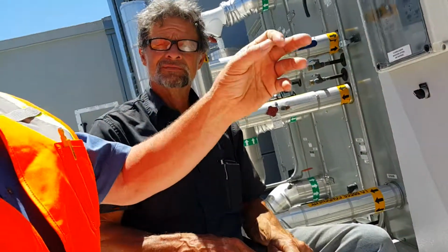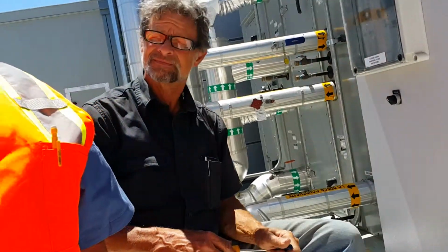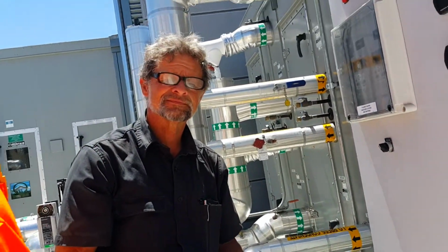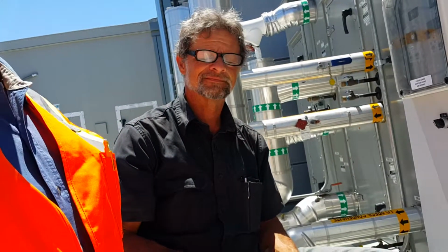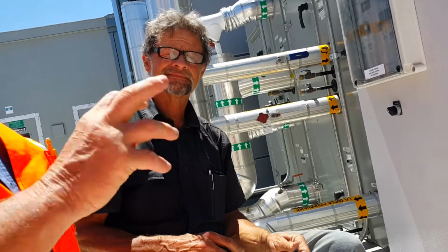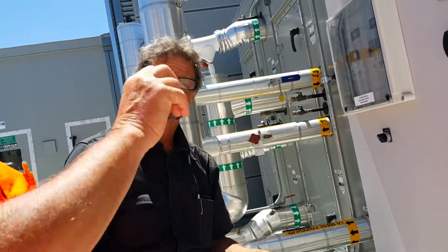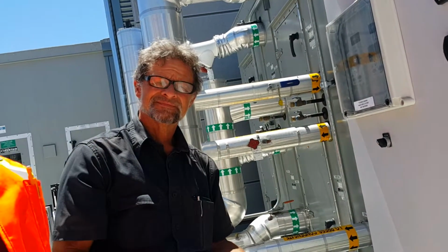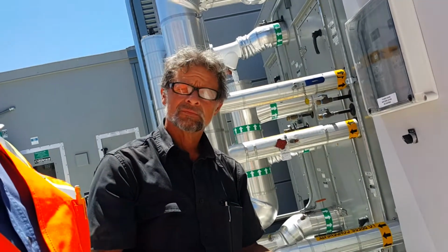We want to label these because you can actually take this head, put it on that unit, or take it over and put it on the other one. Are they all the same, though? They're all the same on this building. Okay. Our drives are the same. They're all interchangeable. So we want to label them so we don't put the wrong parameter head on the wrong unit if somebody starts spinning. But they are all interchangeable though, right?